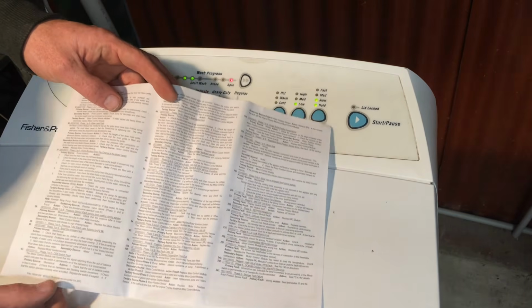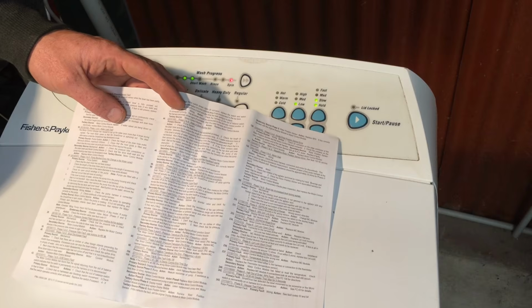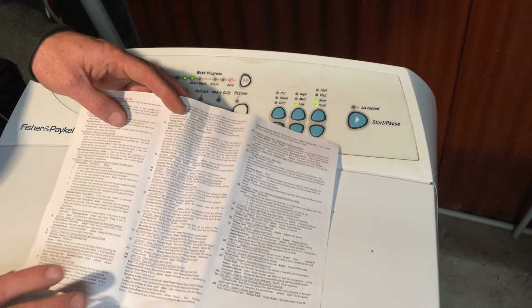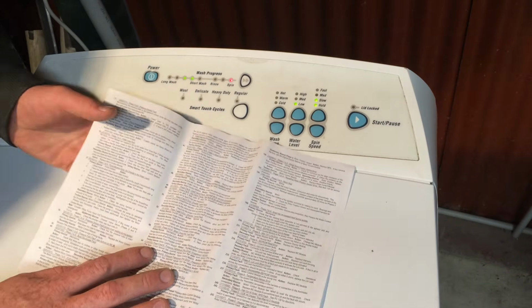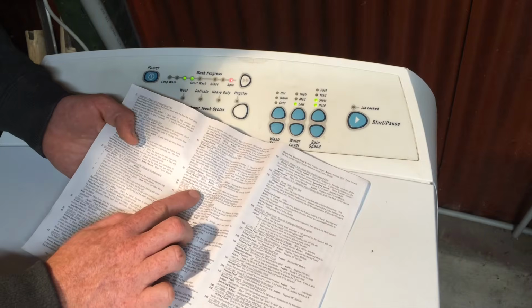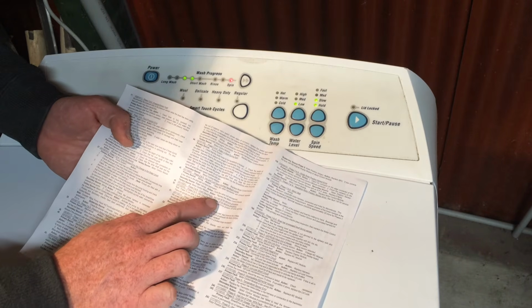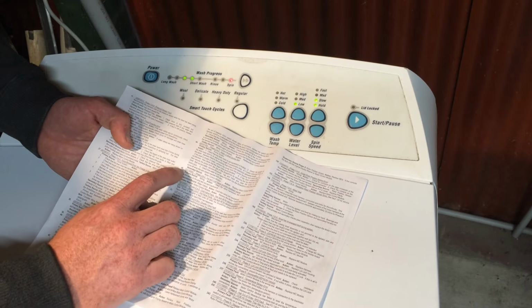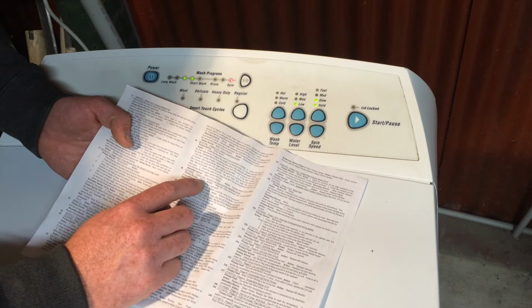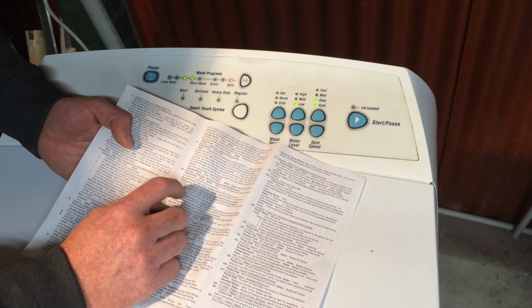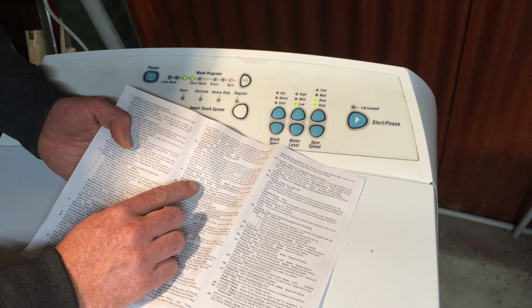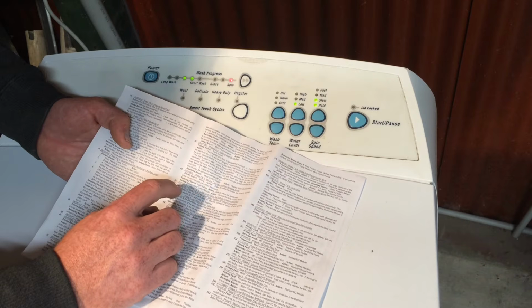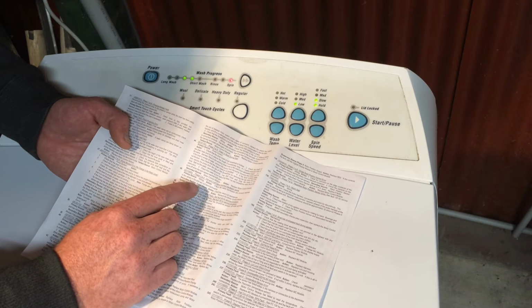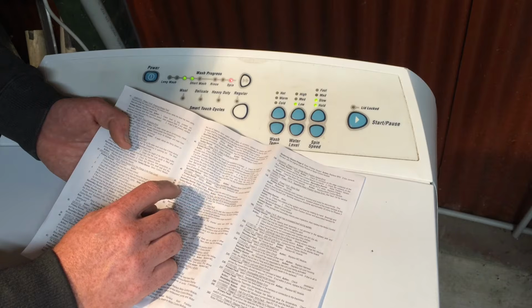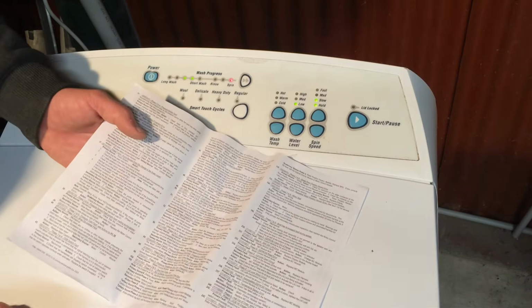On the back here is an abbreviated list of the most common codes, and in a minute I'm going to go through and tell you what usually causes them. If we go to code 49, it says phase 2 to 6, cold valve faulty, C48 for service procedures. And then in 48 it says hot and cold valve incorrect feedback signal. Primary source wiring, check valve harnesses are correctly fastened to the valves. Secondary source water valves, check the valve coil resistances. And tertiary source is motor control module.